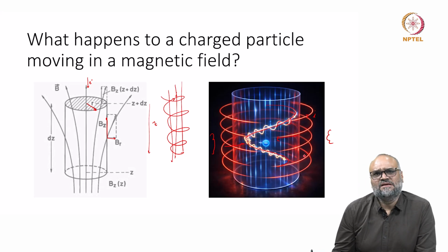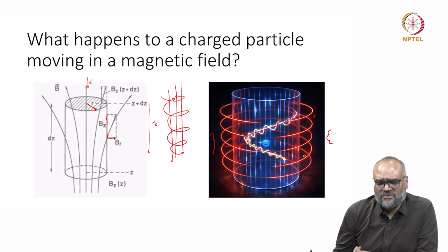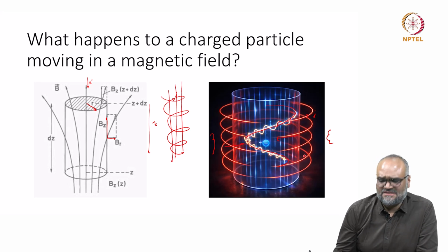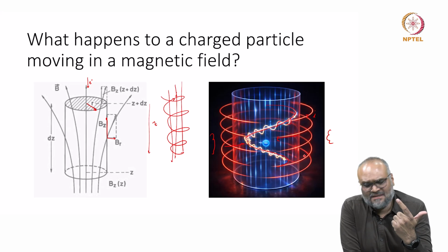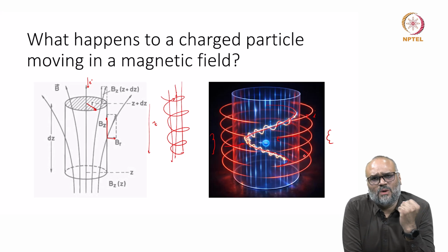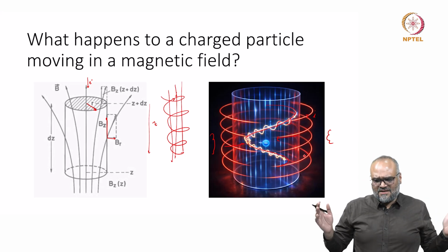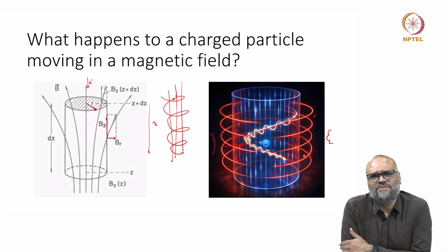You can use a combination of two coils which are called dipoles. You can use quadrupoles, you can use hexapoles. There are multiple constructions of these kinds of coils and arrangements, which is a combination of a current carrying conductor and a soft ferromagnet to simply apply a very high field. Typically, the strength of this field is anywhere between 1 to 2 Tesla, and with this you are controlling the trajectory of your electron beam.